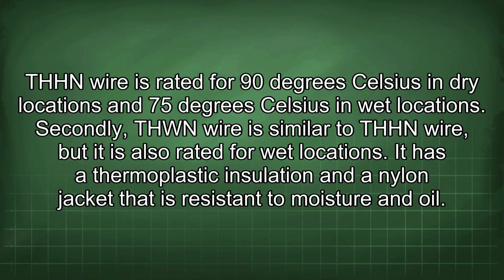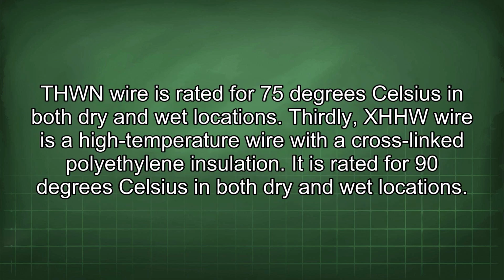Secondly, THWN wire is similar to THHN wire, but it is also rated for wet locations. It has a thermoplastic insulation and a nylon jacket that is resistant to moisture and oil. THWN wire is rated for 75 degrees Celsius in both dry and wet locations.